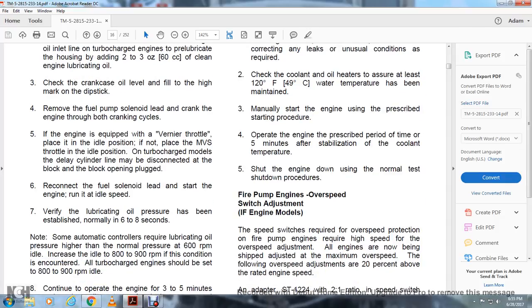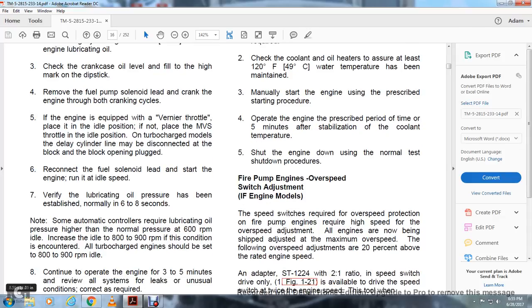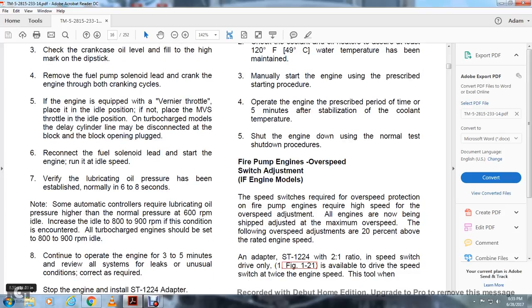The lubricating oil pressure should be established normally within 6 to 8 seconds. Some automatic controllers require the lubricating oil pressure higher than normal at 600 RPM idle, so increase the idle to 800 to 900 RPM as conditions require. All turbocharged engines should be set with an 800 to 900 RPM idle. Continue to operate the engine for 3 to 5 minutes, review all the systems, and correct any leaks or unusual conditions as required.